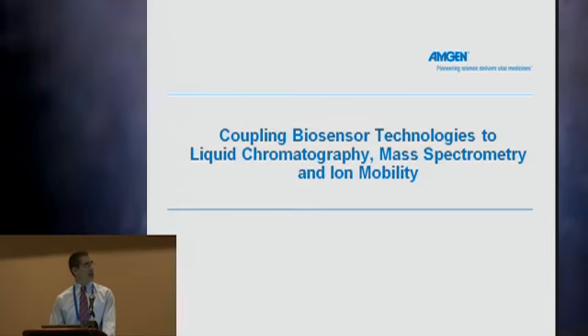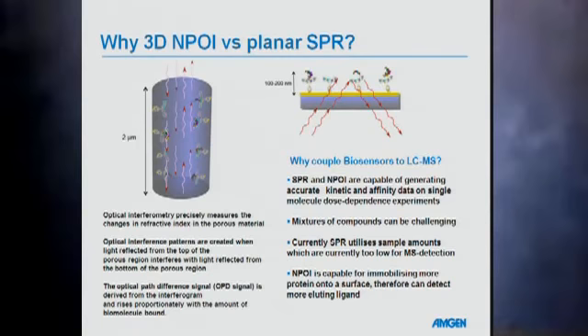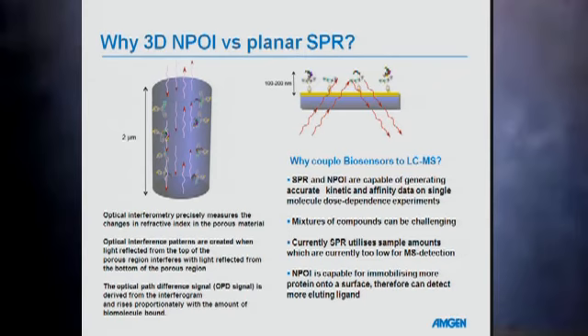In the final eight or so minutes, I'm going to talk about coupling biosensor technologies to liquid chromatography and mass spectrometry. Biosensors allow you to immobilize a protein or enzyme of interest to a surface, then flow over small molecules, peptides, or proteins, and measure the binding constant — the on rates, off rates, and KDs. That's very important in biopharmaceuticals because you want to understand how well a small molecule binds to a target of interest. What we've chosen is nanopore optical interferometry, which essentially measures precisely the changes in refractive index in a pore in the presence and absence of a binding small molecule. This optical path difference is then deconvoluted and a KD, on rate, and off rate are derived.